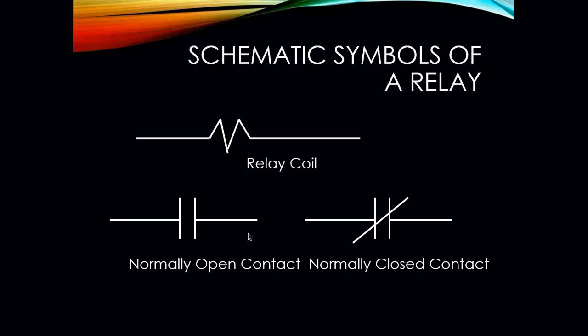When you see the coil and relays on a schematic, these are the symbols that you're most likely going to run into. You have your coil, which is doing all the work. You have our normally open and our normally closed contacts. Between our normally open, we have terminals 1 and 3. Between our normally closed, we have terminal 1 and terminal 2. So anytime I energize this coil, this set of contacts is going to close. This set of contacts is going to open. Remember, they're going to do the complete opposite than what they are normally in.